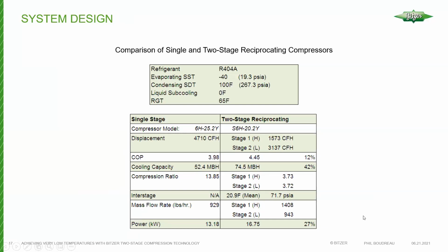Okay, so another way to compare the single stage and the two stage. This is very interesting. This will show you the difference in performance for a compressor that is a single stage versus a two stage, but with the exact same displacement. So a 4,710 cubic foot per hour compressor in a single stage, and I should really update this slide, because this is the previous version of the compressor. We called it .2 generation, and this compressor now would be an Ecoline, which would be a 6HE version.